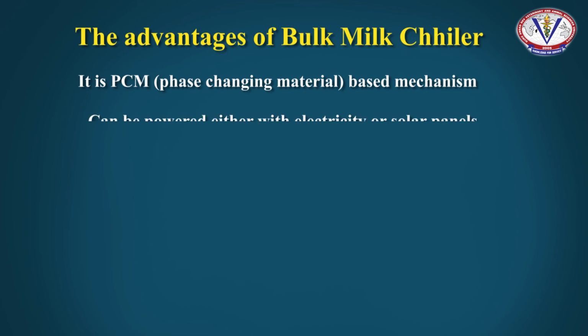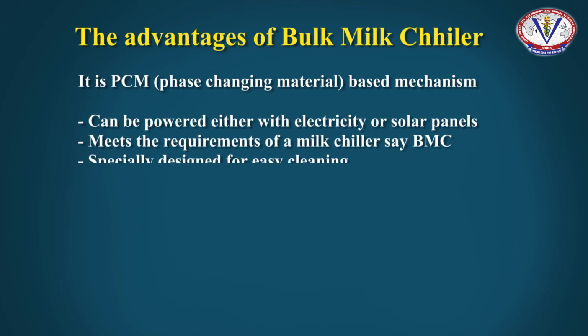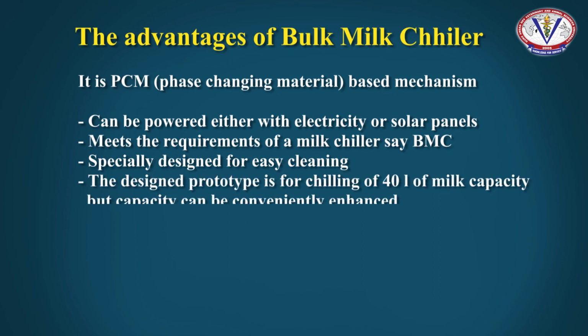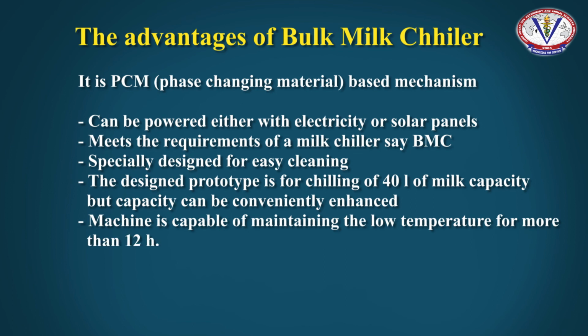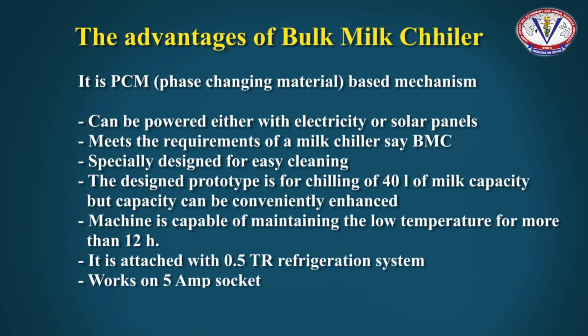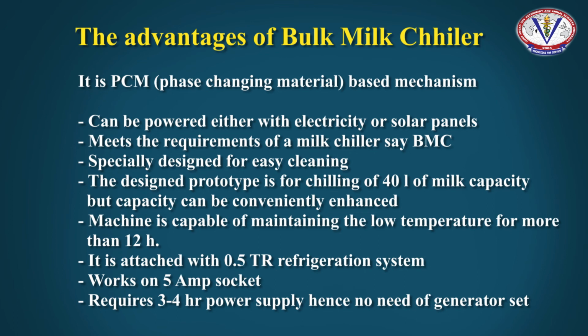In this milk chilling system, a phase changing material based component was introduced, in which the primary refrigerant first converts the phase changing material to the solid phase, and without coming in contact with the milk, this phase changing material chills the milk in the required time of milk chilling, that is 2 to 3 hours. The advantage of using secondary refrigerants or a PCM based refrigeration system is that we can lower the capacity of the primary refrigeration system by almost half.